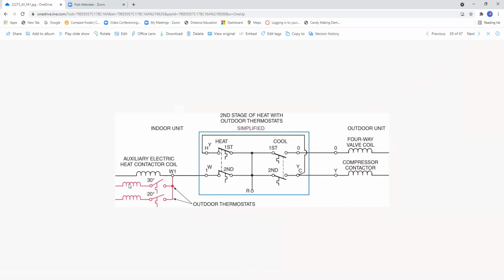And notice that each one of these strips has a sequencer. Basically, they don't both energize at the same time. Typically, you're going to energize the relay, and then we have a sequencer which will energize one stage of strip heat, and then later on it'll energize another stage of strip heat. And then we have an outdoor thermostat, which is going to allow which stages to come on in this case.